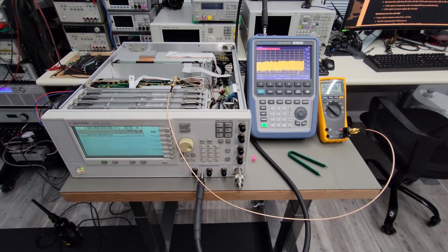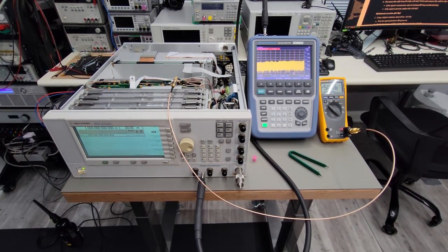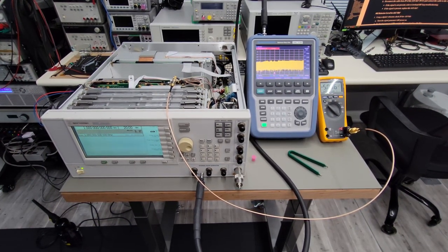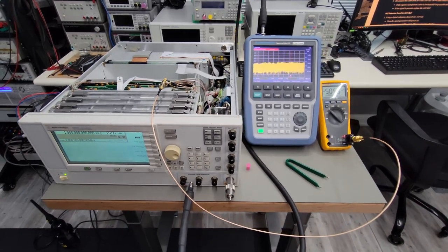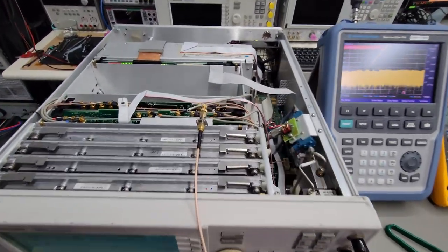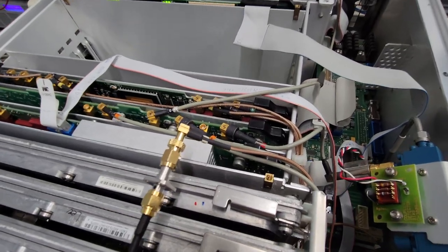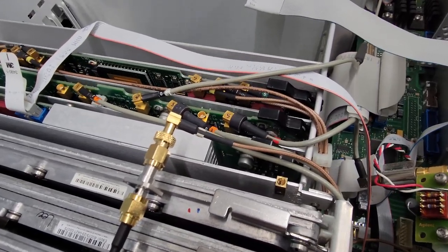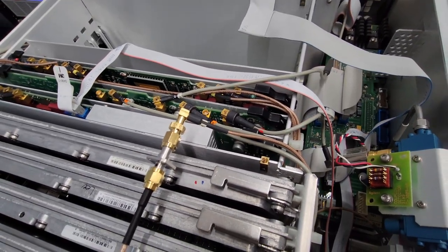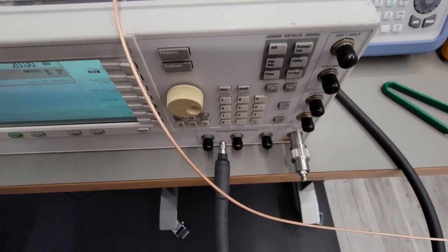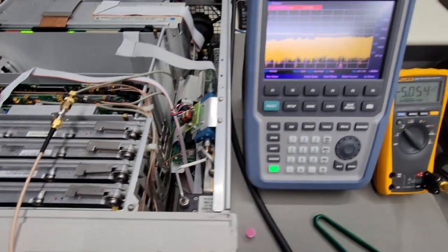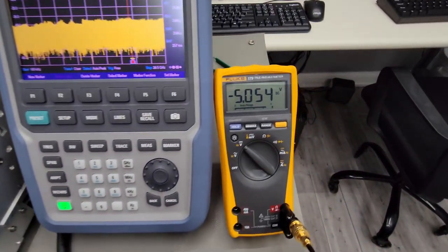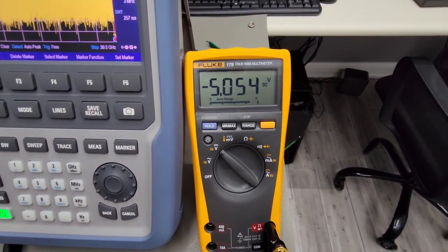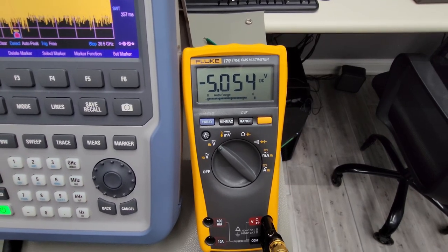At this point, I'd become suspicious that the remaining issues with this instrument were not hardware related, but rather software related, in relation to losing the calibration memory that the instrument had from the factory. So before sending this unit out for adjustment again, I'd made some final measurements on the ALC loop just to be sure that the internal detectors were not the issue. All the measurements I made seemed to line up with what was suggested in the service manual, so at this point I knew the instrument needed to be adjusted.